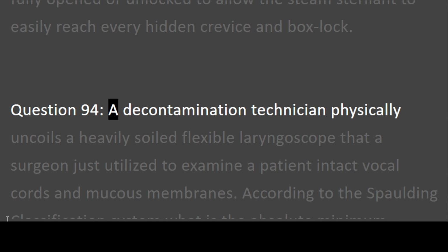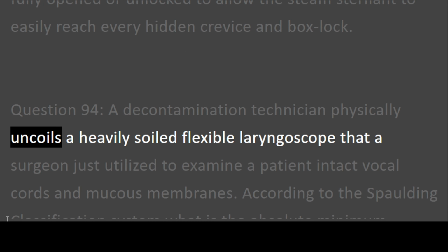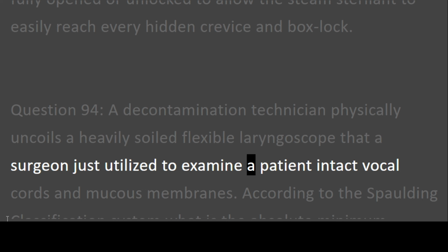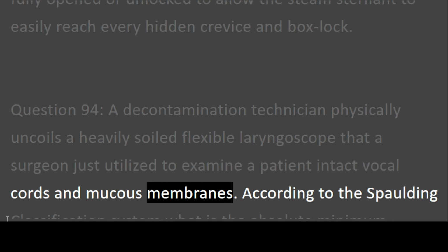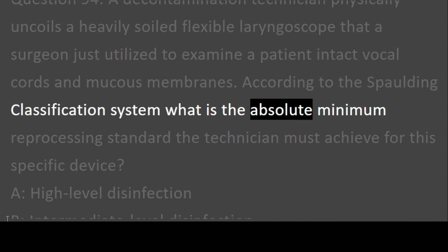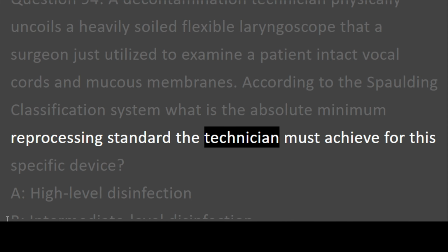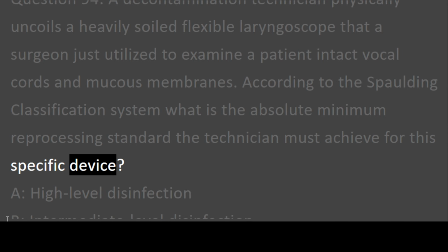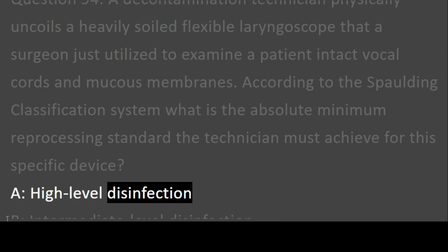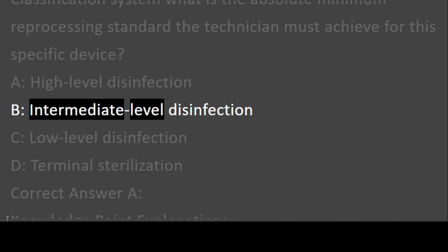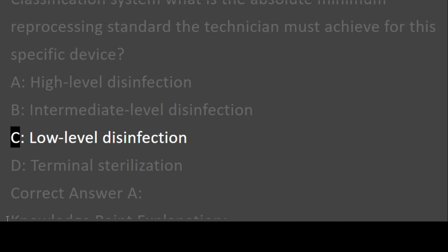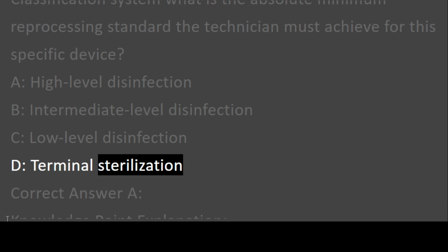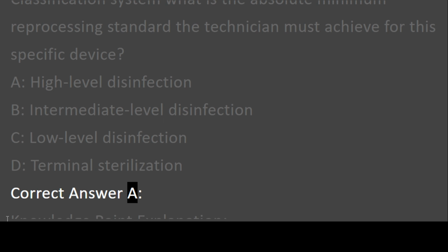Question 94. A decontamination technician physically uncoils a heavily soiled flexible laryngoscope that a surgeon just utilized to examine a patient's intact vocal cords and mucous membranes. According to the Spaulding classification system, what is the absolute minimum reprocessing standard the technician must achieve for this specific device? A. High-level disinfection. B. Intermediate-level disinfection. C. Low-level disinfection. D. Terminal sterilization. Correct answer A.